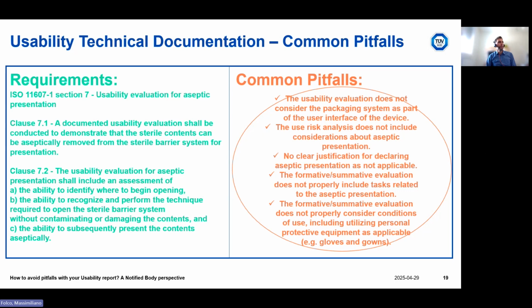Common pitfalls are the following. Usability evaluation does not consider the packaging system as part of the user interface of the device. The user risk analysis does not include considerations about aseptic presentation. So these are two basic errors: missing to recognize that the packaging system is part of the user interface of the device, and missing to consider aseptic presentation as an input for the user risk analysis. No clear justification for declaring aseptic presentation as not applicable, as I explained before. The formative and summative evaluation does not properly include tasks related to the aseptic presentation, and does not properly consider conditions of use, because when the tasks related to the unpacking, so to the removal of the device from the packaging, this phase is performed in certain conditions.